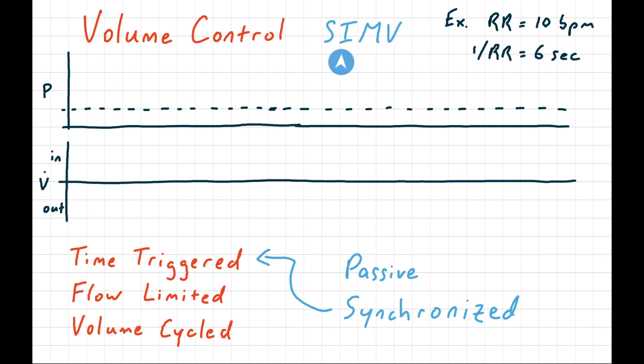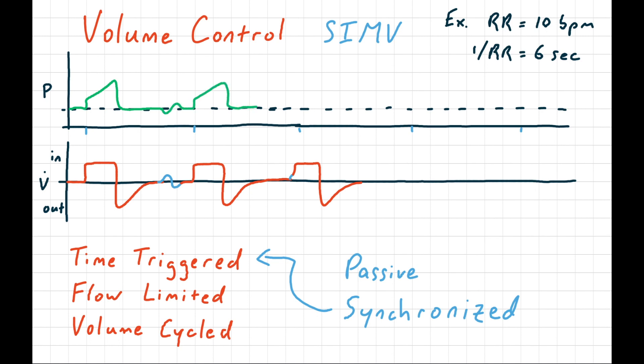The next iteration is called synchronized intermittent mandatory ventilation, or SIMV. It's exactly the same in terms of allowing extra unassisted breaths, but it's kind enough to say: if you try to take your own breath and it happens to be about when I was going to give you a breath anyway, I'll start the programmed breath at that point. So if the patient started taking a little breath near a timed breath, the ventilator would synchronize its effort with the patient's breath. The advantage is that the patient isn't drawing against a closed valve, and if the patient is breathing slightly faster than the programmed rate, they don't wind up in a dyssynchronous rhythm fighting the ventilator.